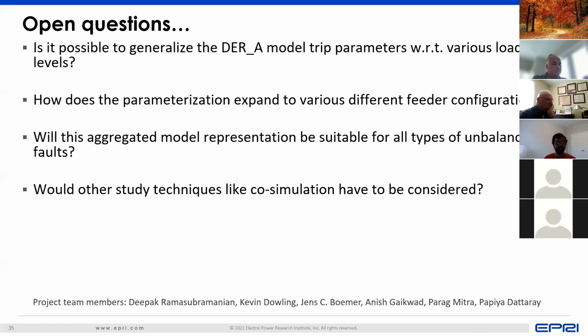Yeah, definitely. So there are a few key differences between what we call distribution and transmission. One is the voltage level. The transmission system pretty much operates at higher voltage levels, maybe 230 kV, 500 kV, levels like that. Usually the way we split up our system, of course, this is not a one-size-fits-all demarcation, but generally we say anything above 69 kV is considered transmission system.